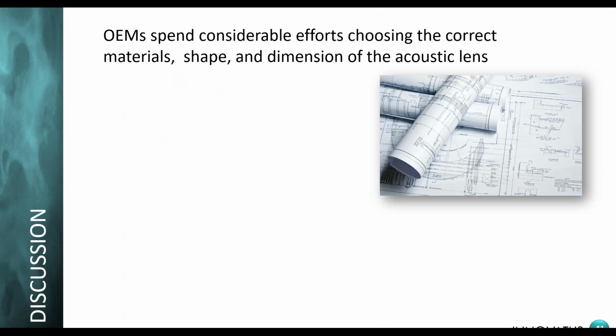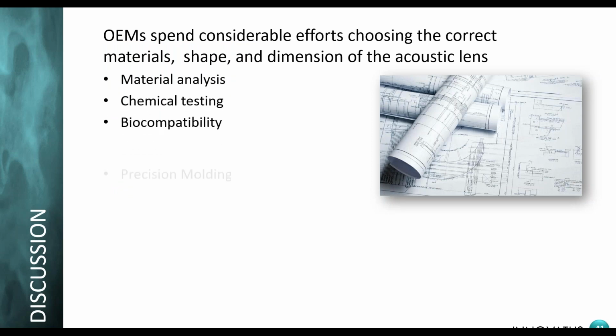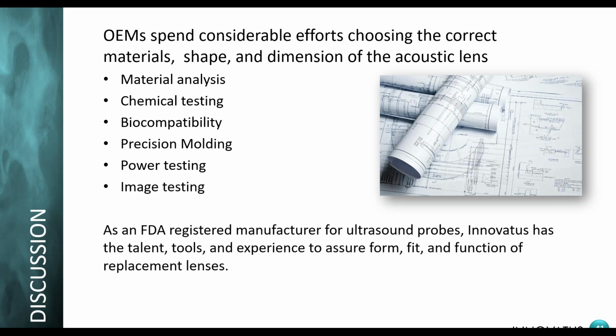So OEMs spend considerable effort choosing the correct material, shape, and dimension of the acoustic lens. So we have to do material analysis, chemical and biocompatibility testing, and precision molding. And then power testing. When we create a lens, we do power testing. Are we still putting out the same amount of power, no more, no less, than the OEM intended? And then we do image testing.